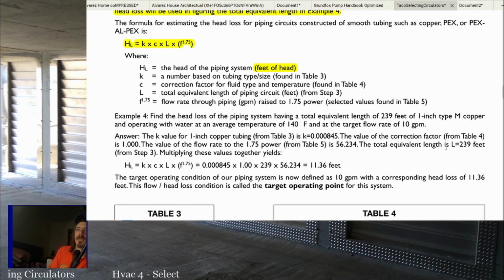All right, so find the head loss of the piping system having a total equivalent length of 239 feet, 1-inch M copper, and operating with water at an average temperature of 140 and a target flow rate of 10 GPM. So we figured out we have 239 equivalent feet of pipe in the previous steps. We know we want 10 GPM from the previous steps, and the temperature of 140 is what you're going to pick based on your system. So you would actually find that number in the real world.